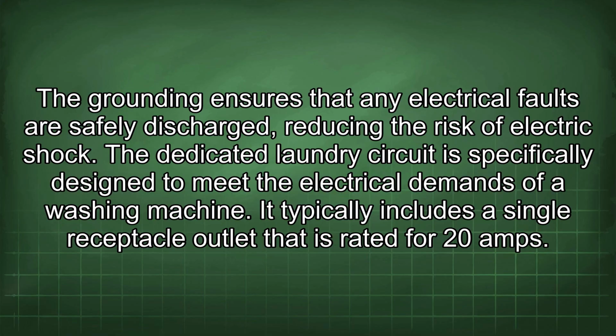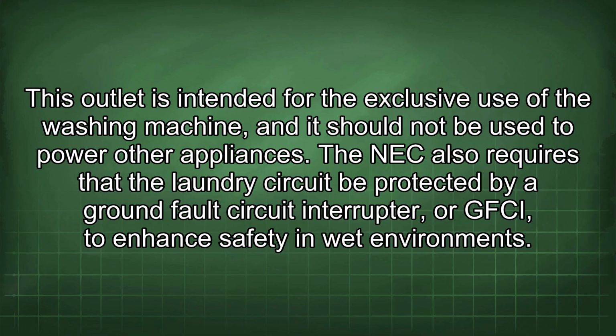The dedicated laundry circuit is specifically designed to meet the electrical demands of a washing machine. It typically includes a single receptacle outlet that is rated for 20 amps. This outlet is intended for the exclusive use of the washing machine, and it should not be used to power other appliances.